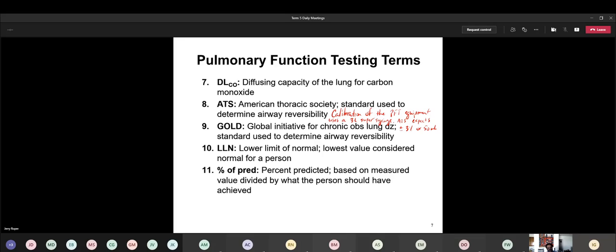That's not a lot of room, as you see. It's got to be really, really close. So if your machine is measuring more than 3%, whether it's higher than 3 liters or lower than 3 liters by more than 3%, then you got to redo the test. You got to keep redoing it until you get a number that falls within that very narrow, like 3% margin. That's one of the requirements.